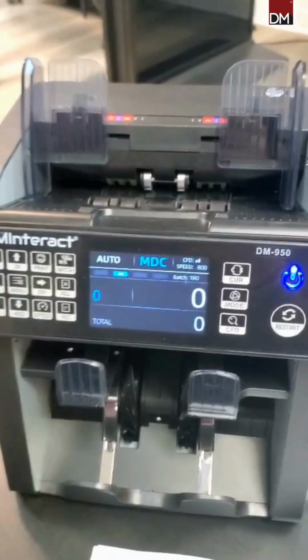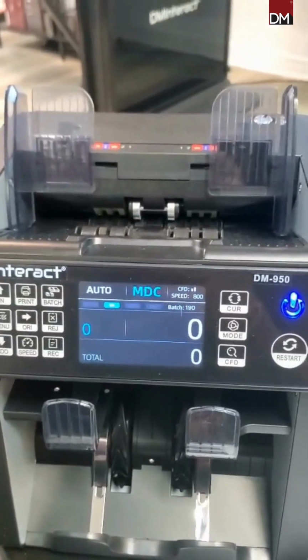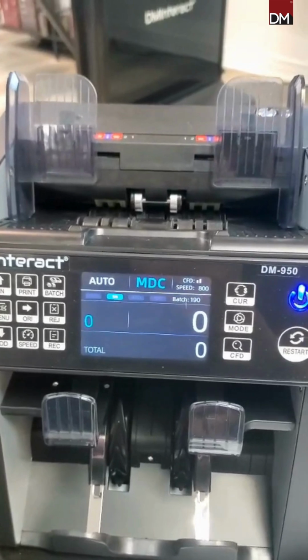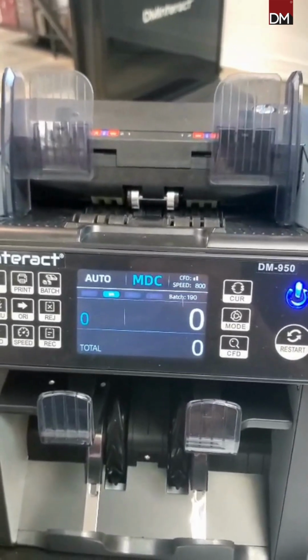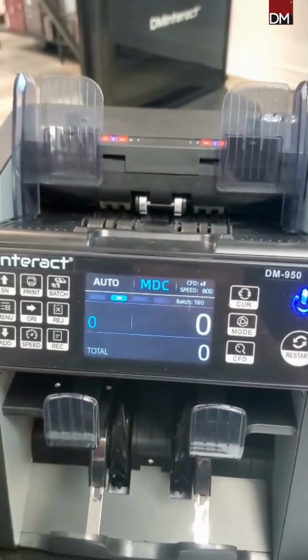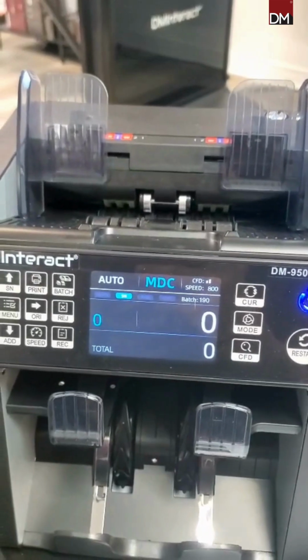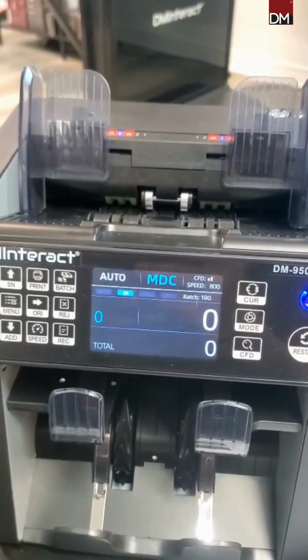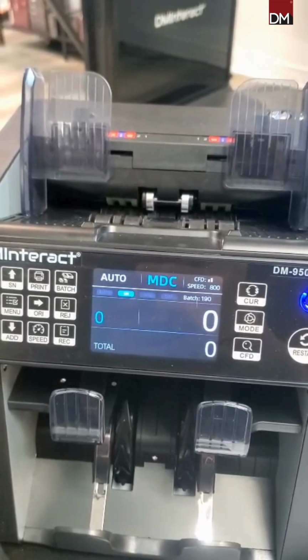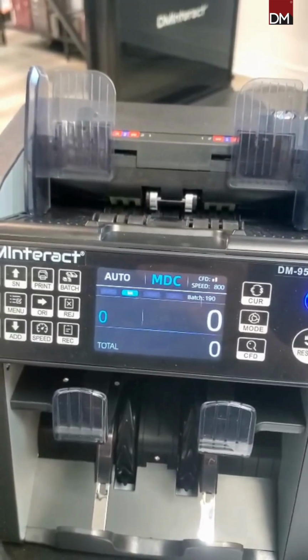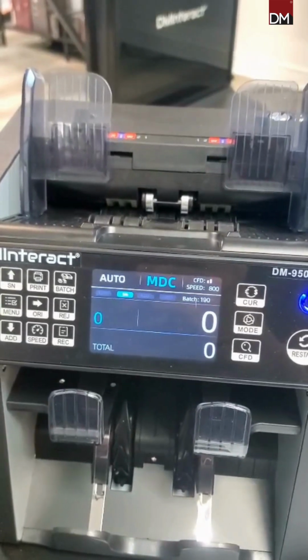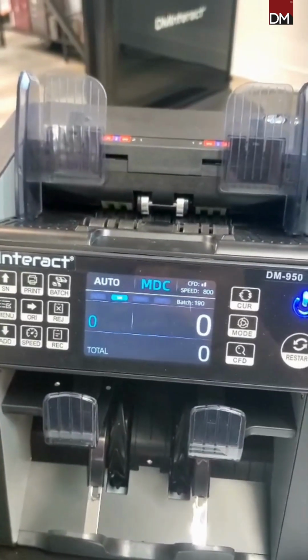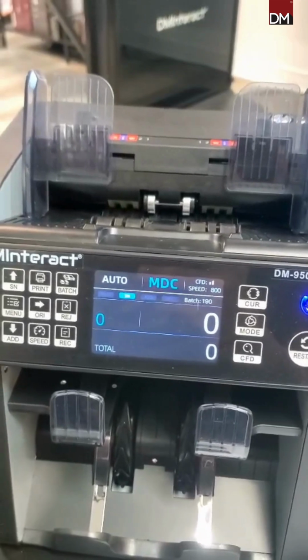The last thing I want to talk about is the maintenance. Now, as you know, after starting the machine, it will go on self-check automatically. If the preset window over here shows that there's an error code or it tells you to clean the sensors, generally speaking, it is because of dust that is on the surface of the sensor blocked by the notes. So please clear the dust on the surface with a brush or a soft cloth, or take the notes away and then restart the machine.